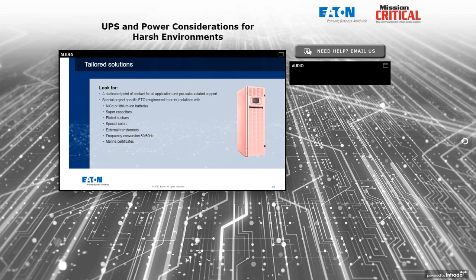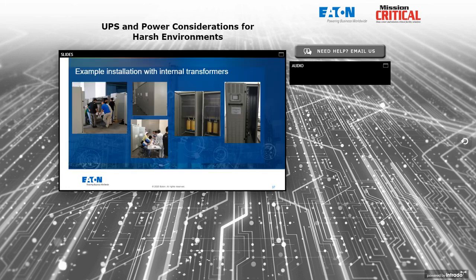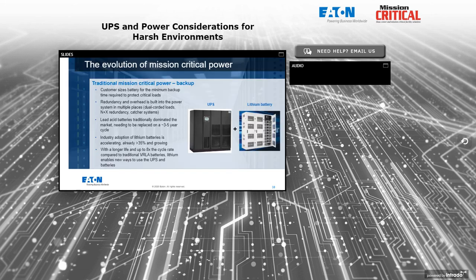Remember that these types of UPSs will not have the luxury of a bypass, since the frequency of the output is different than the input. But frequency converters are common for most UPS vendors that make industrial UPS. And then the necessary certificates for marine application that we saw in one of the previous slides. This shows a couple of shots at installation for a transformer-based industrial UPS where the transformers housed in the cabinet along with the UPS electronics, the way we used to do it back in the good old days.